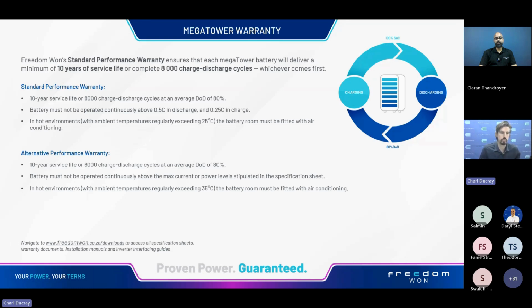The warranty works with 2 performance options: a standard and an alternate performance warranty. The standard performance warranty offers 10 years service life or 8,000 charge/discharge cycles at an average DoD of 80%. With this extended number of cycles, the battery should not be operated continuously above 0.5C discharge or 0.25C charge. In hot environments, where ambient temperatures regularly exceed 25°C, the battery room should be fitted with air conditioning. That's a more conservative C rating, which works in the battery's favor and ensures longevity over the long term.